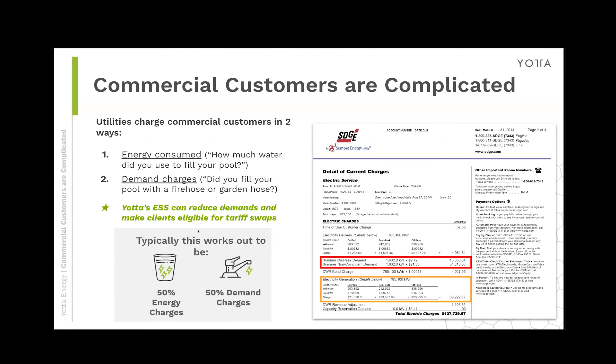A quick review on how commercial clients are billed: they're charged for energy charges and also separately for demand charges — how much electricity is being used in a given instance. This is different from your residential customer. If you add solar to a building, you're really attacking the electric generation, not so much the demand charges. When we talk about NEM and the devaluation of solar credits, adding batteries to bring back the ROI and savings that customers were used to seeing under NEM 2.0 requires adding peak shaving to win back those customers and get their ROIs to where they need to be to sign off on projects.